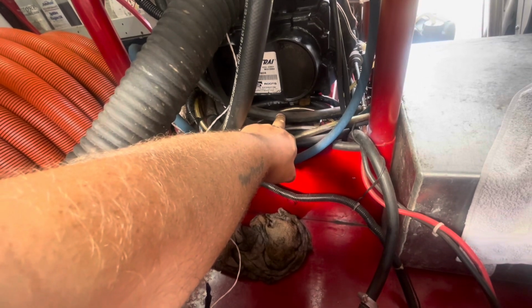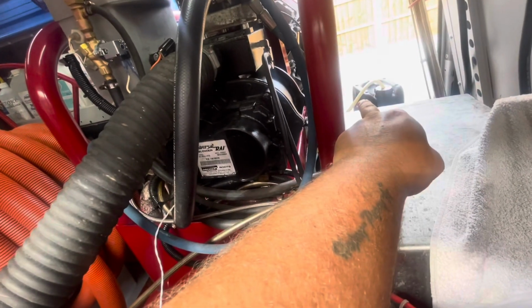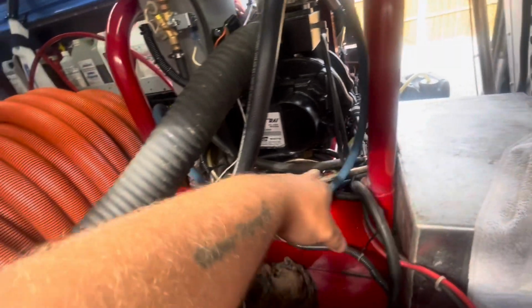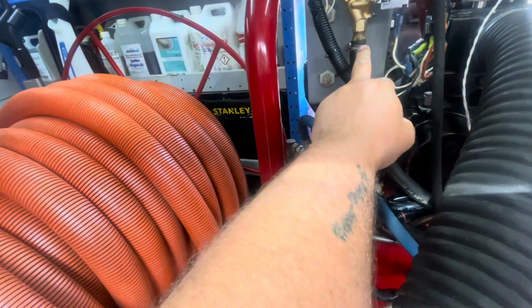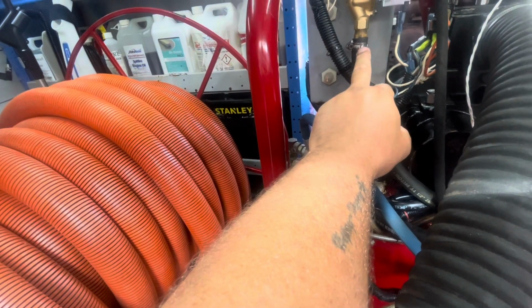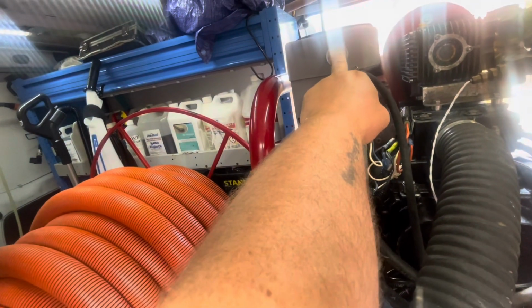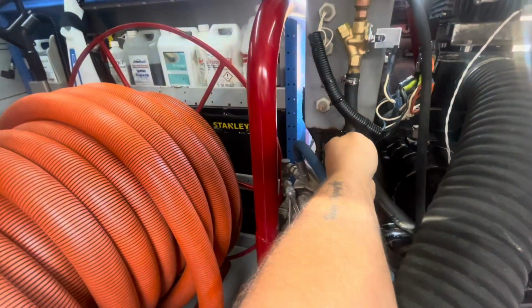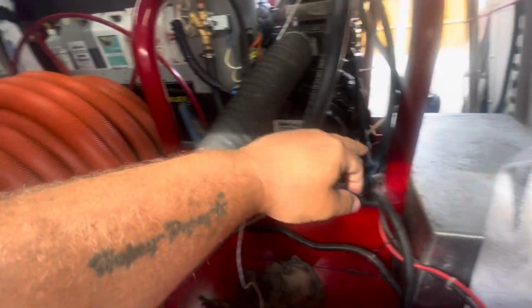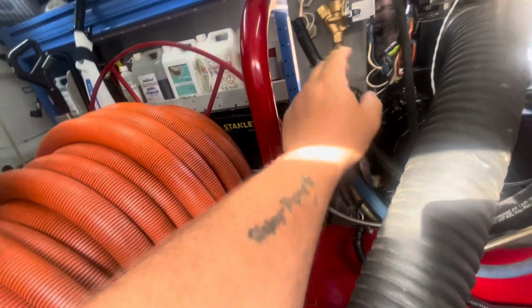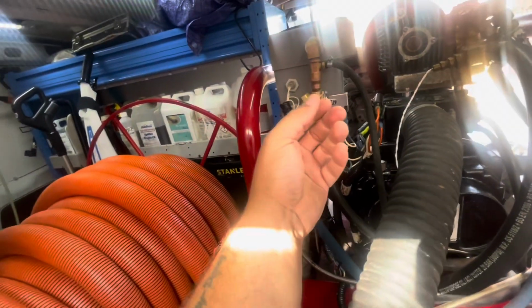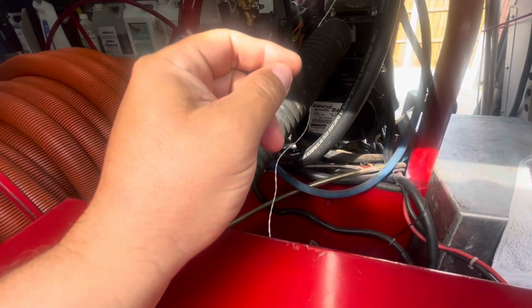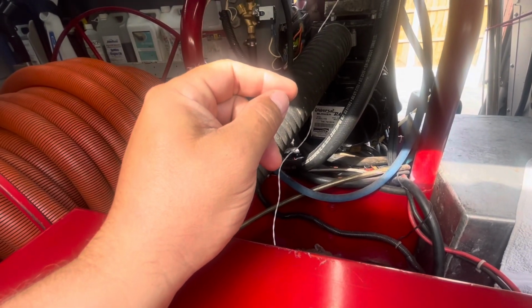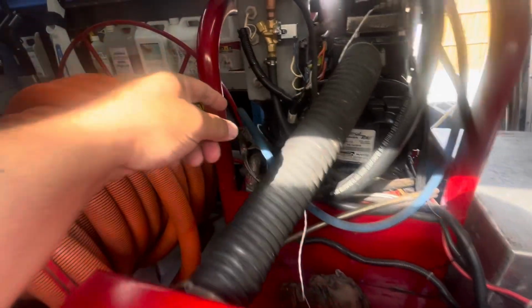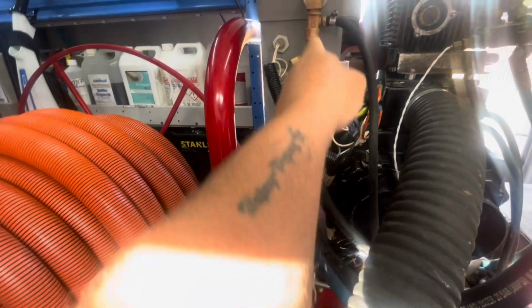So, tracing the hose that fills the header tank from the female connect at the front, it comes up and goes up to here. So what I did was disconnect it from the top, and squeeze the pipe all the way round and down. No water was coming out the top when this was off, which told me there was either a blockage in the pipe or something going on in this bit here.